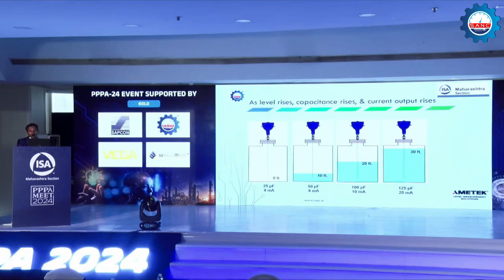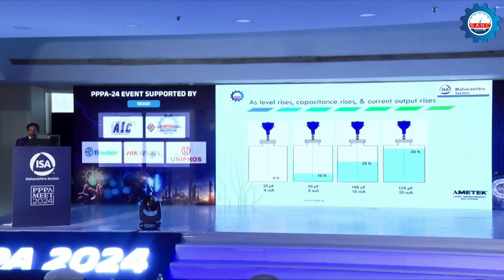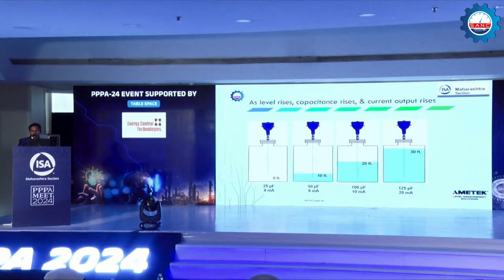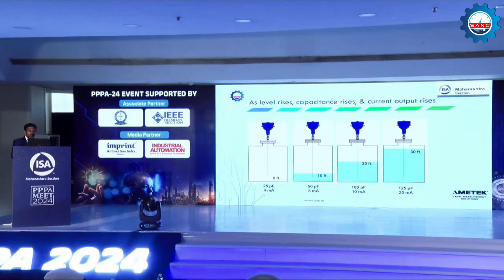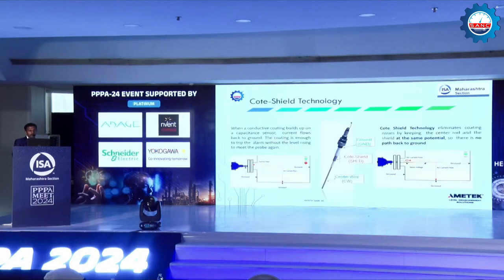But one common problem with this technology is, what if the medium is sticky? If there are sticky materials in the vessel that we have to measure, they will remain on the probe even though the actual level comes down. To overcome this, Ametek Drexelbrook level measurement solutions has developed a unique technology called Cote Shield. This is a patented technology by Ametek Drexelbrook.